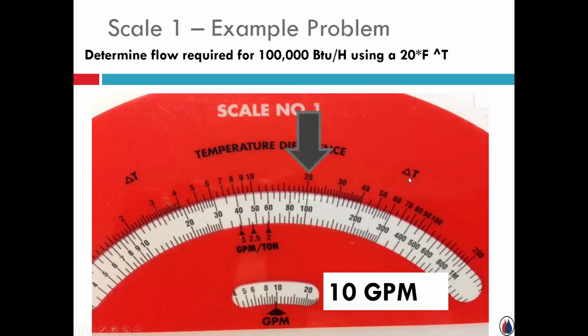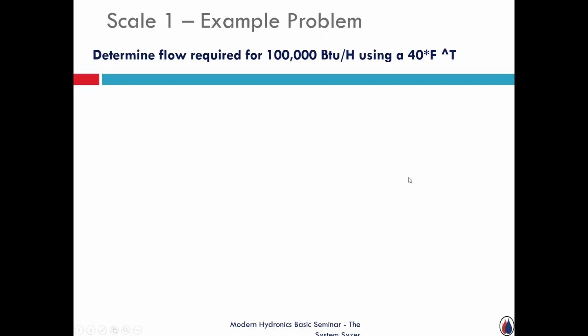It's as simple as that. That's what that scale one's all about. Change it. Say, hey, same load, but I'm going to design, I'm going to open up that delta T. We talked a little bit about it last week because it can influence flow rate, which means pipe size and pressure drop. But instead of designing it on 20, let's make it 40.